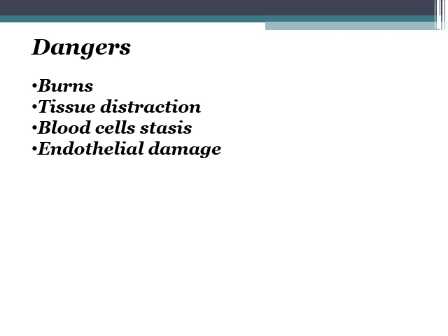Before that we covered physiological effects, which include thermal effect and non-thermal effect. If we want more thermal effect, then we have to use continuous mode. If we want more mechanical or non-thermal effect, then we have to use pulsed mode to dissipate the heat, right? So accordingly we can choose our mode of application of ultrasound, right?